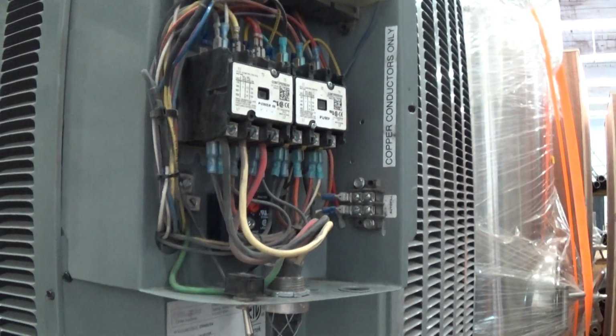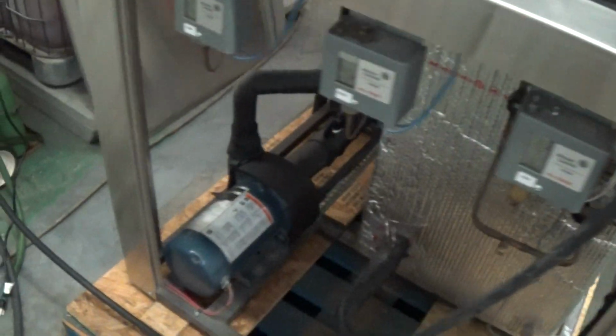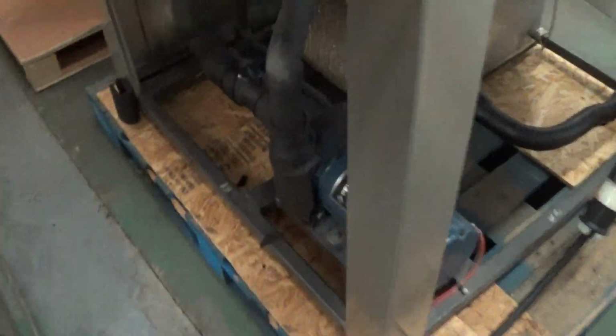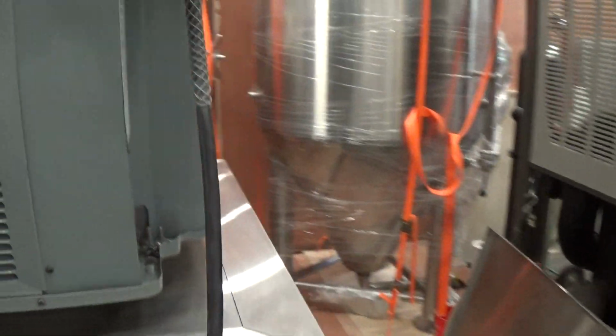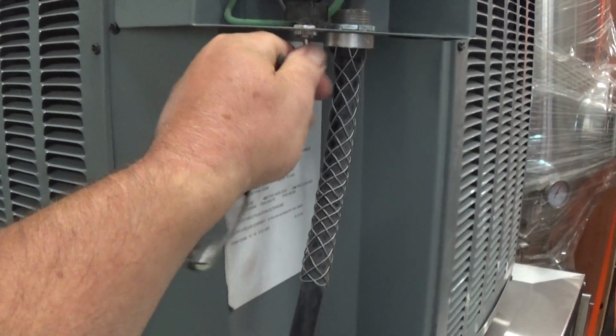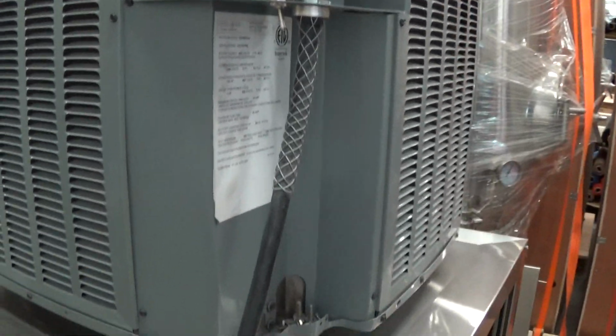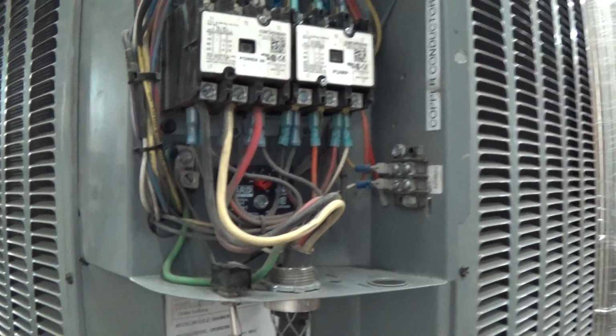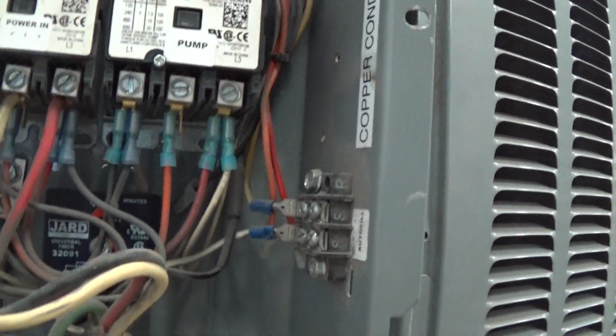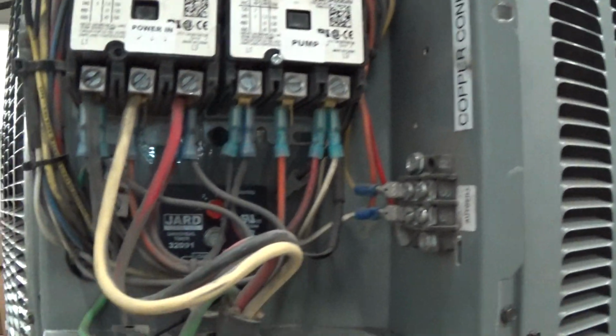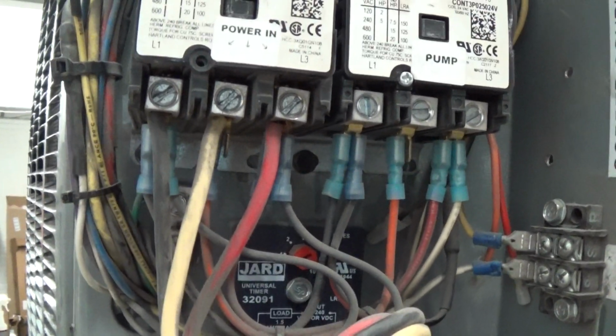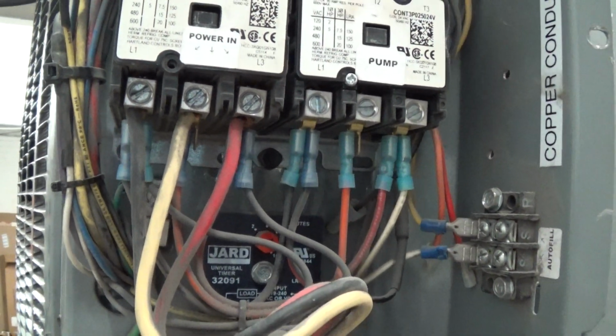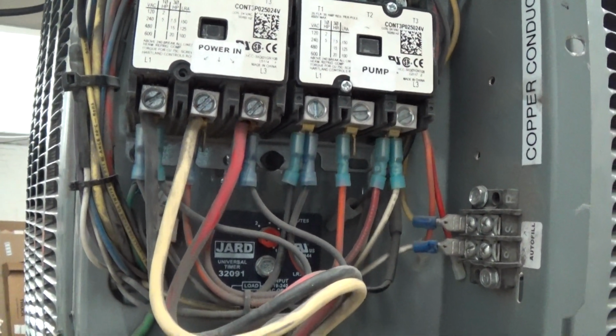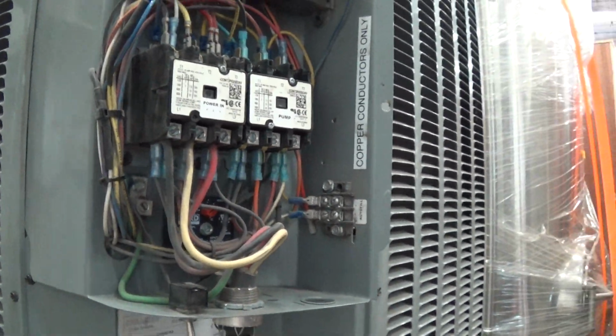But you do have to check for phase rotation. The simplest thing is to get somebody to come down with a flashlight, look at the side vents of the pump, and toggle the power quickly and make sure it's rotating clockwise. If it is not rotating clockwise, then you change the incoming power. Don't worry about the contactor that says pump, because that's already synchronized with the compressor. If it's not rotating clockwise, you're just going to swap any 2 of these 3 leads. Or have your electrician do that, which is the correct thing to do.